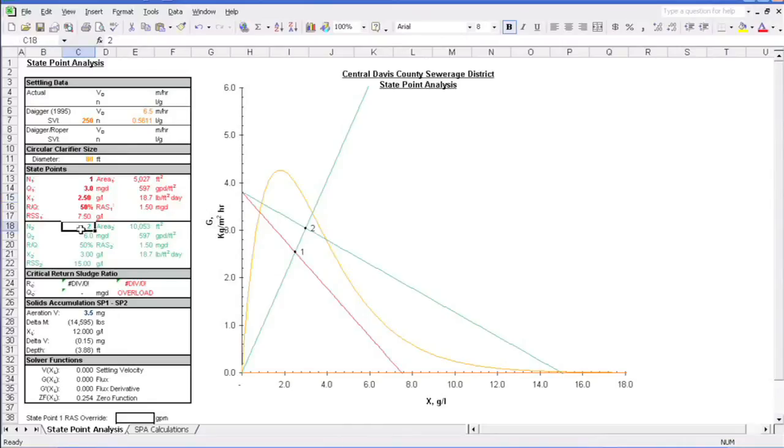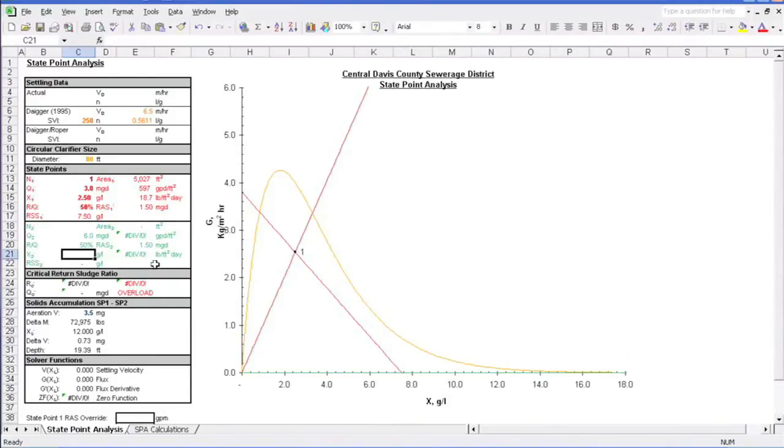Let's clear the second state point values now so we can focus on our single state point. And as you've probably noticed, this model adjusts the graph automatically and immediately, allowing us to quickly evaluate how things are going. Well, we see that in this case, things are going quite well. Both the state point and the underflow line fall under the settling curve. Man, life is good. The sun is shining, birds are chirping, and the air smells fresh. Well, as fresh as a wastewater plant has to offer. But just like any rainstorm can ruin a perfect day, it can also ruin your smoothly operating clarifier.